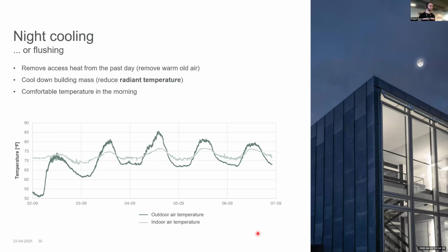But what we also see from the results in projects is that by cooling down the building mass, as shown on this graph, you can actually keep a nice, comfortable indoor temperature at an acceptable level, as shown here, even on days where the outdoor temperature gets pretty high. This is due to the building mass and will vary from project to project, and it is why the architecture is so important, because these kinds of results are only possible if we have a building that's really designed with the building mass, not having excessive solar gain, using efficient solar shading, and not having a large glass facade oriented towards south.